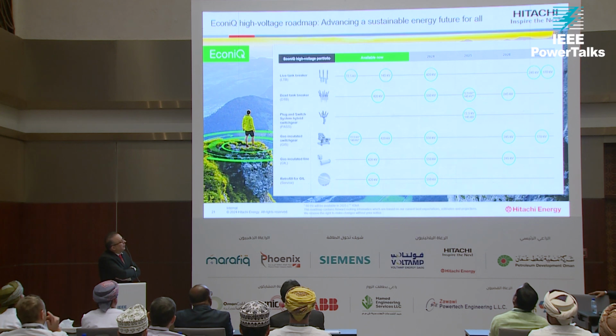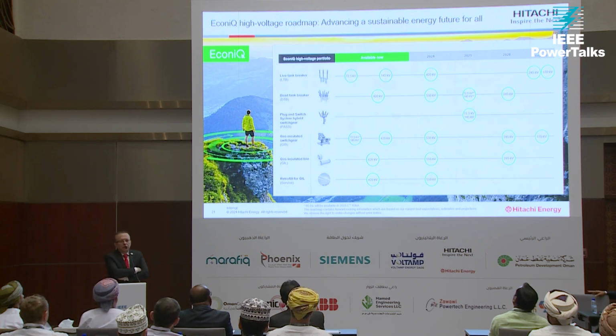The other categories, dead tank breaker, PAS, and gas-insulated switchgear, all work based on the concept of metal enclosed breaker, MEB, and in that one we also have another gas mixture.